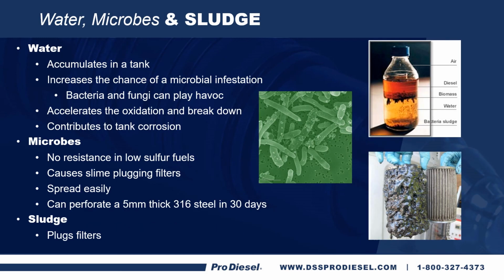As previously stated, 95% of all fuel has some amount of water in it. It accumulates in the tanks. It increases the chance of microbial infection. You get bacteria and fungi that can just wreak havoc on a fuel system. It also accelerates the oxidation and breakdown. Now we know that 26% of degradation happens in just the first 28 days, so we don't need it to break down any faster than what it already does. And it contributes to tank corrosion.